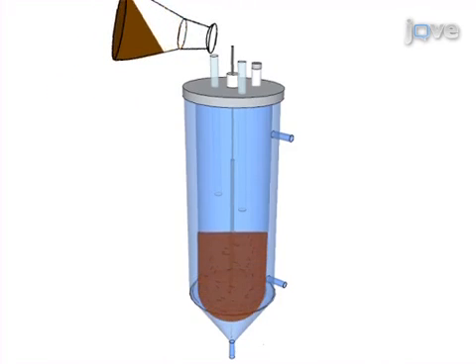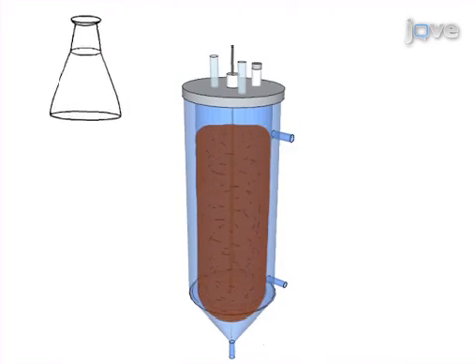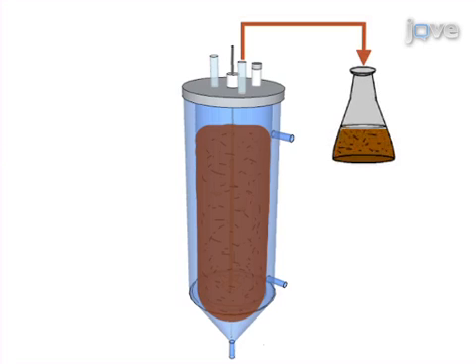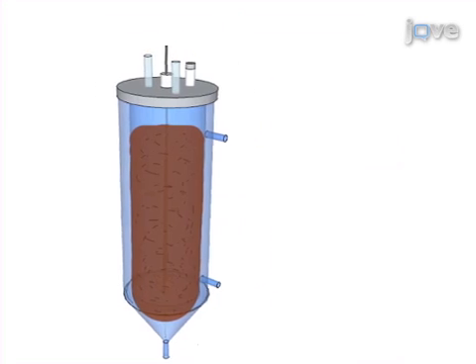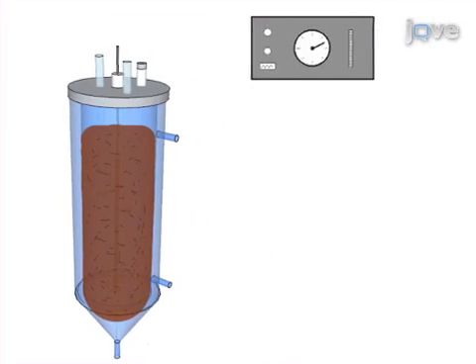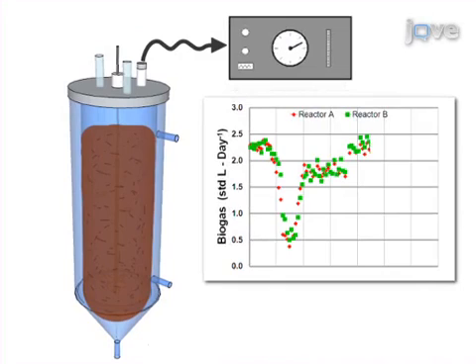Inoculation is done with active methanogenic biomass by establishing a suitable anaerobic environment within the bioreactor system. Then the proper operation of the digester system is described, including effluent decanting, feeding, and troubleshooting. The final step is to introduce a monitoring strategy to assess digester performance and stability using standard analyses conventionally used in the field of anaerobic biotechnology.